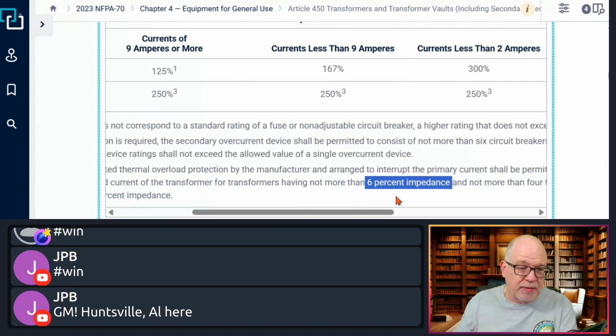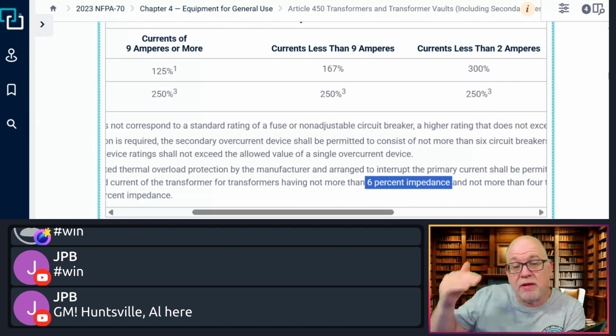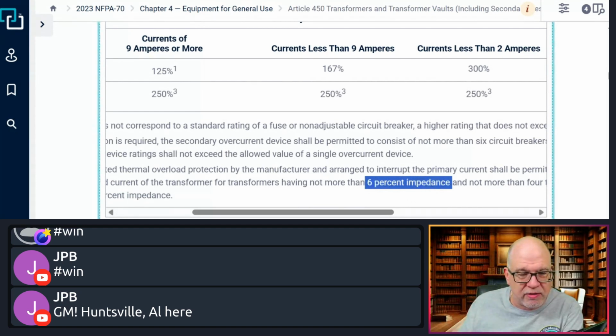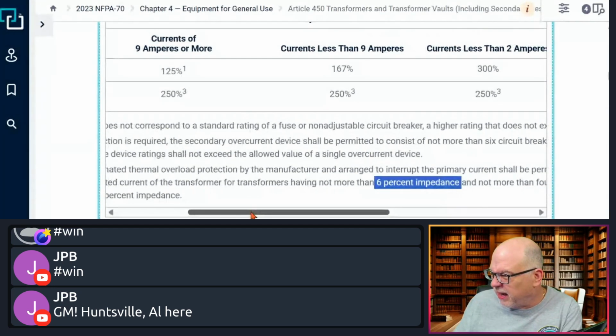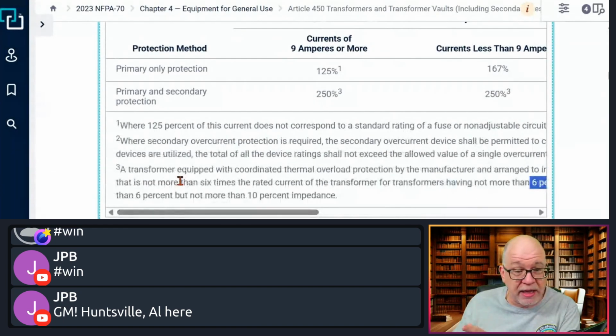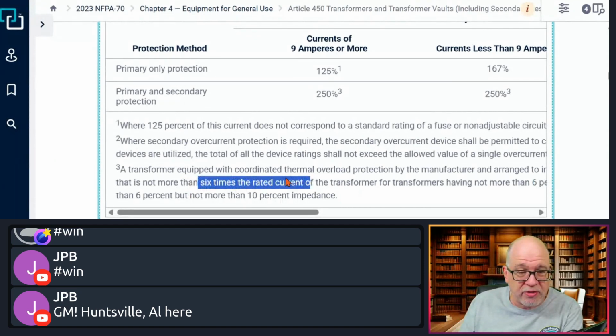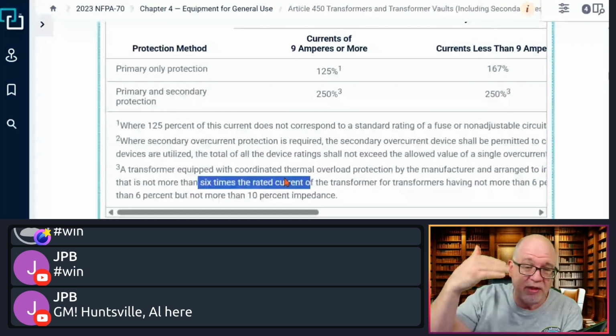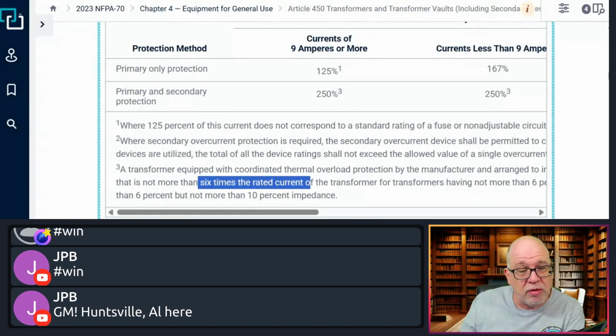So we'd have to look at the nameplate, right? We'd have to see what the impedance is on the nameplate. So then we would take the kVA and the voltage and find out what our rated current is. And then it says, okay, if it is not more than 6% impedance on that transformer's nameplate, then I can go not more than, no rounding up, not more than 6 times the rated current. Okay, so whatever the rated current is times 6, if I can't round up to the next size, I'd have to drop down. And the only reason that I can do that is because this is a special type of transformer with what's called coordinated thermal overload protection built into it. It's part of the manufacturer, and you're going to pay for that, okay?